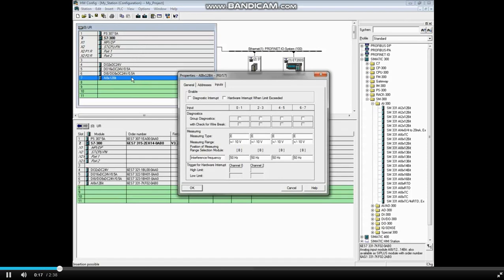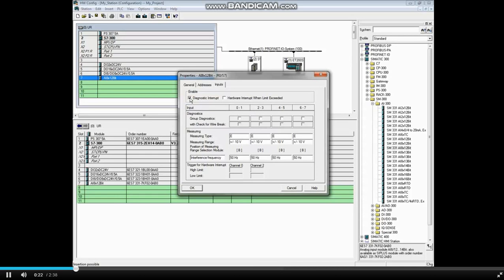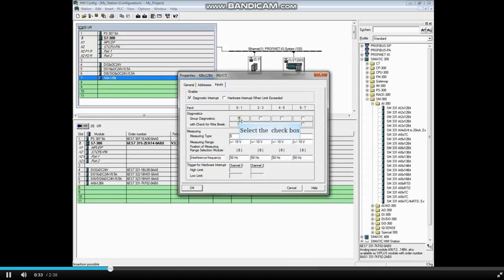To enable diagnostics, put a check in the box Diagnostic Interrupt. Then place a check in the Group Diagnostics box under each channel group that you want to report diagnostics. The first group covers the first two channels or inputs, 0 and 1.